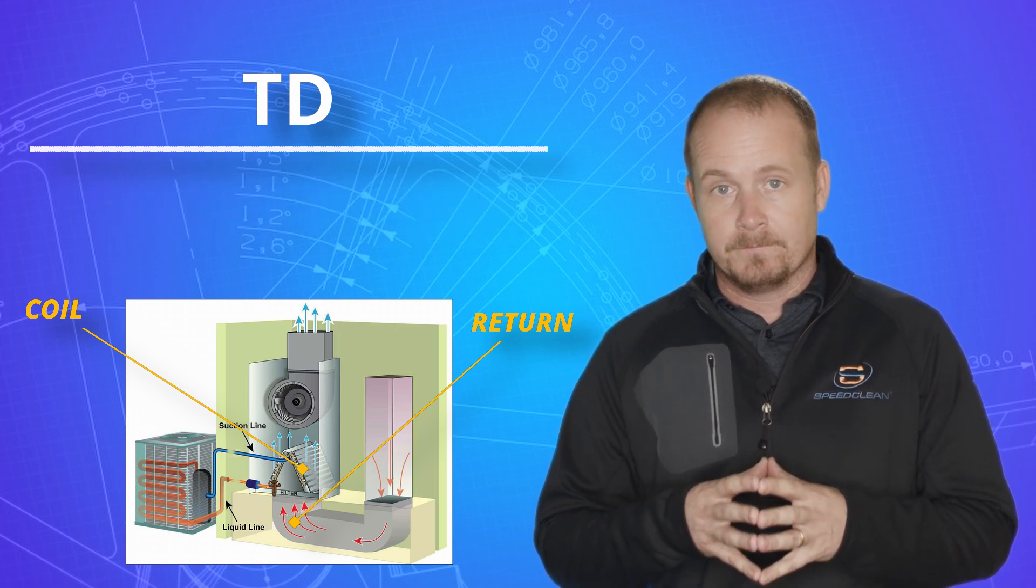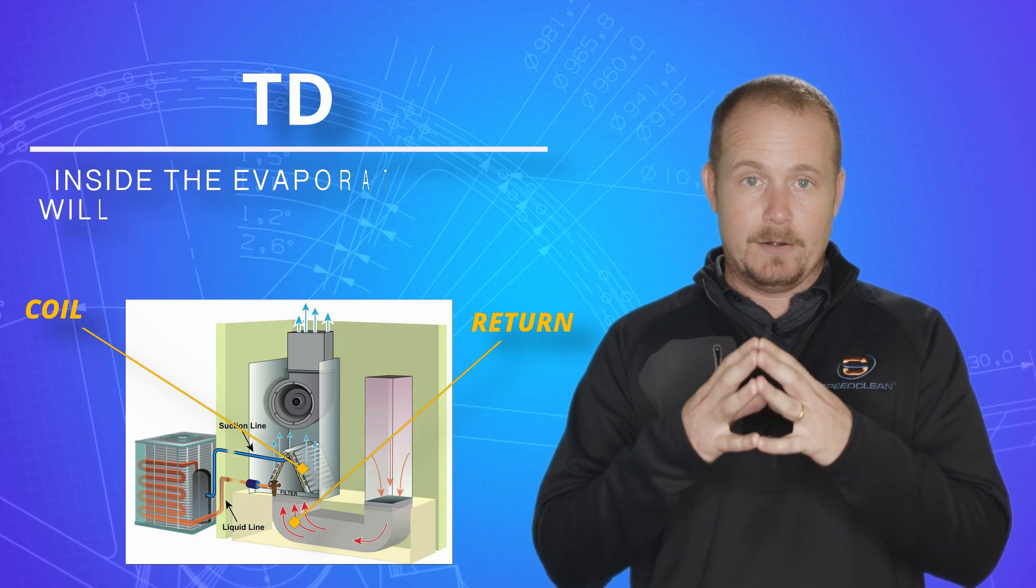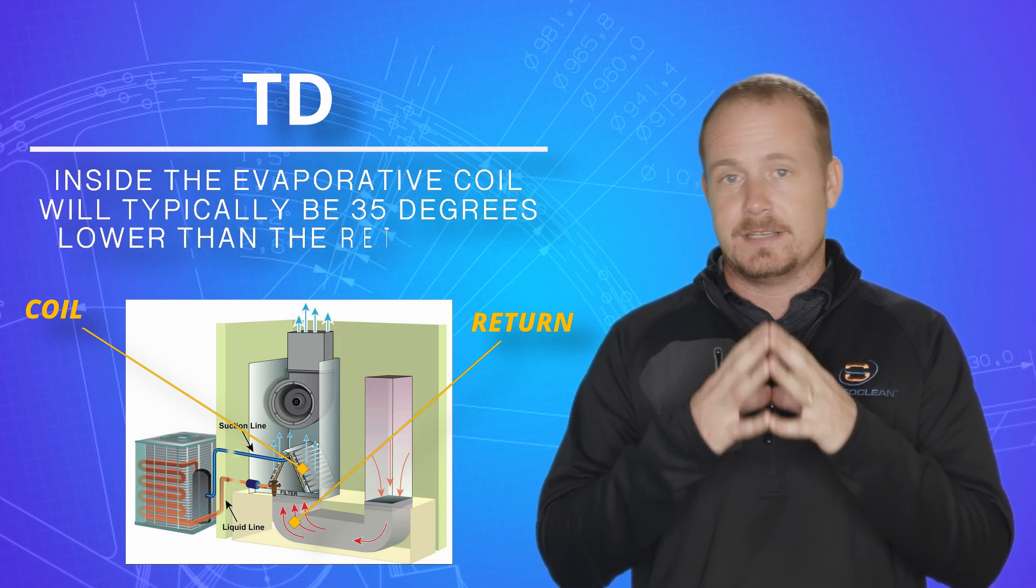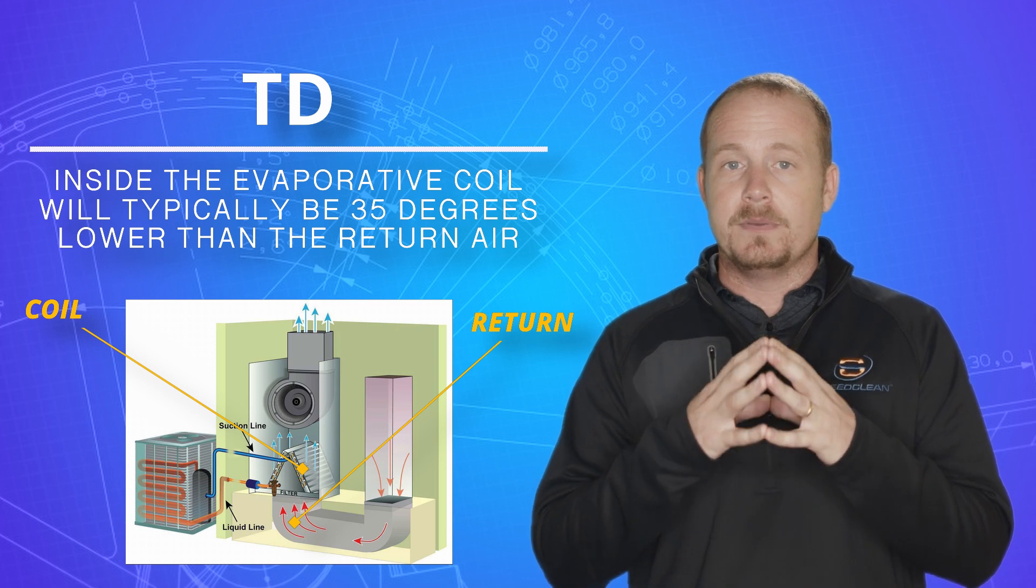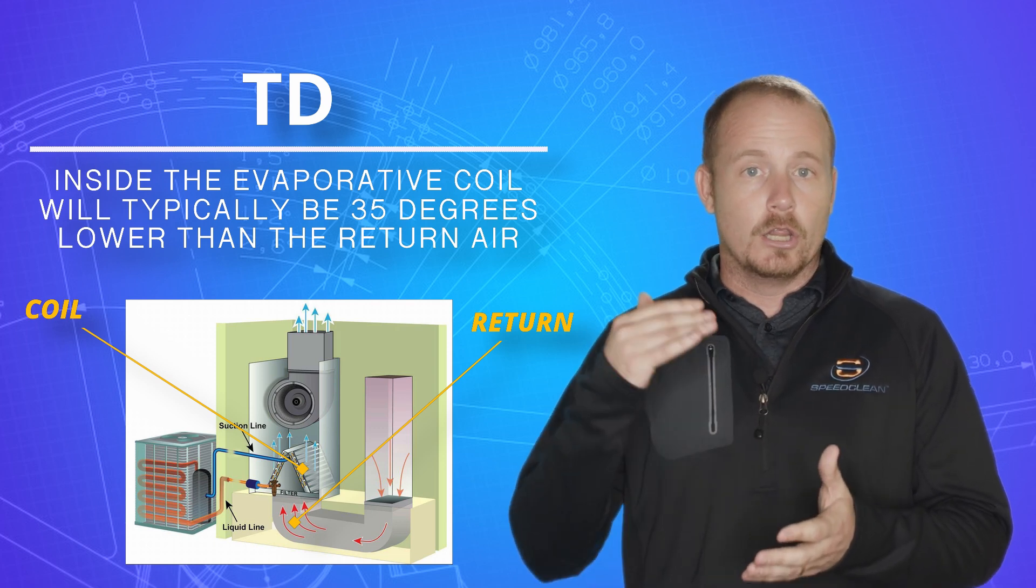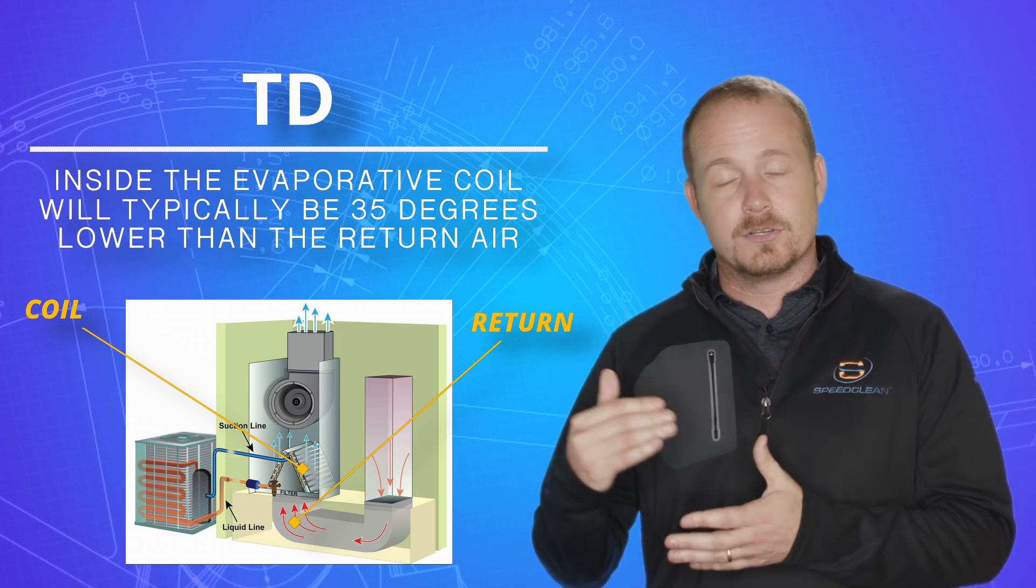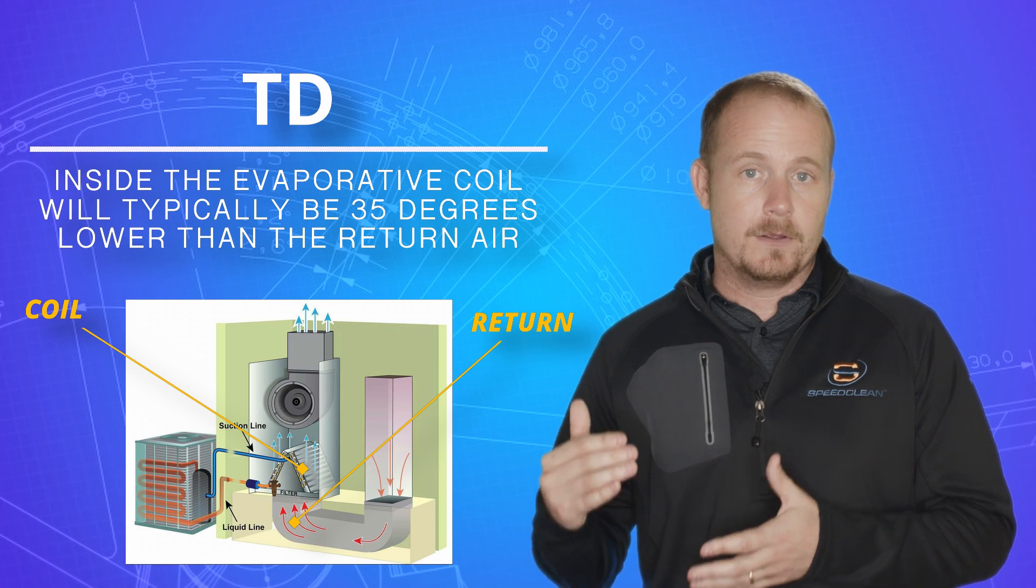But typically 35 degrees is kind of your standard baseline Td that you're going to see. And that means that your evaporator coil inside when it's boiling, when it's at that suction saturation temperature, is going to be about 35 degrees lower than the return air temperature if the system is working properly.